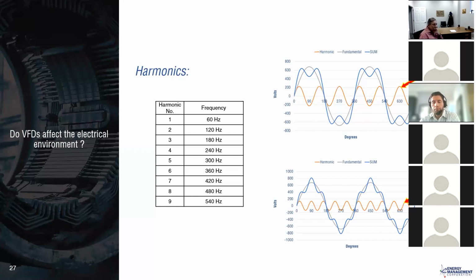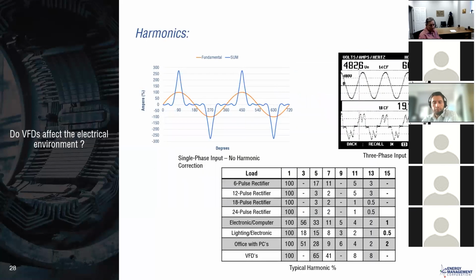This distortion can be broken into individual harmonics, and that is done by the Fourier transform, of course, and that is what we refer to as total harmonic distortion of voltage or current. What that means is, for example, total harmonic voltage distortion is the total effect of all voltage harmonics on the fundamental. So that's what total harmonic distortion means. Getting into the current harmonics, this is how a current harmonic looks, that you see in the blue color.